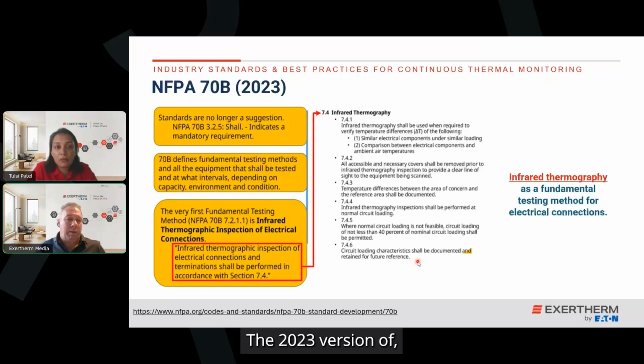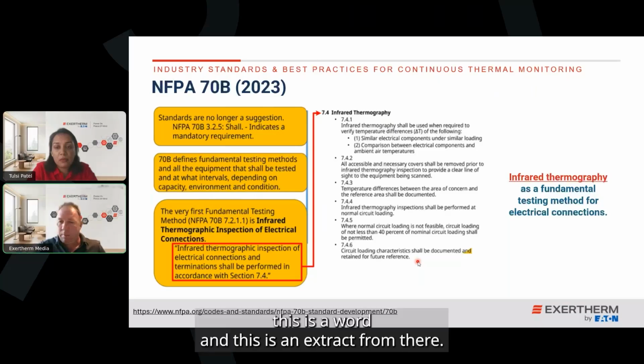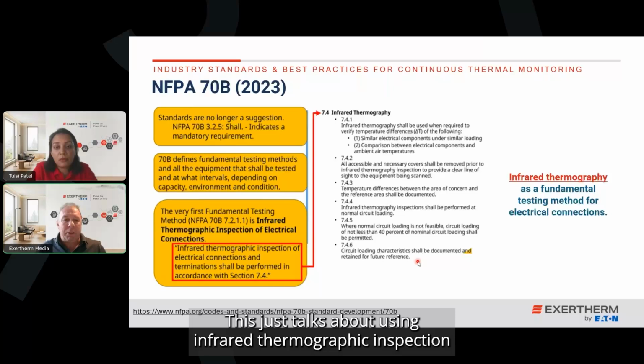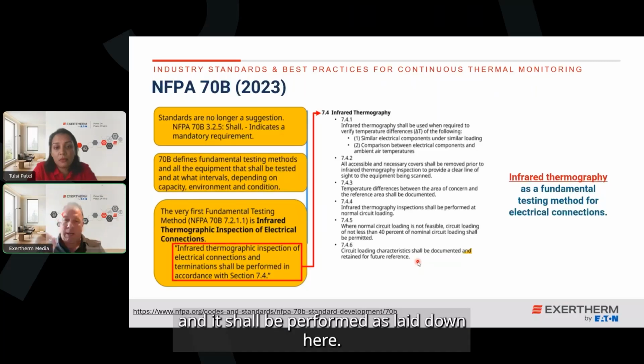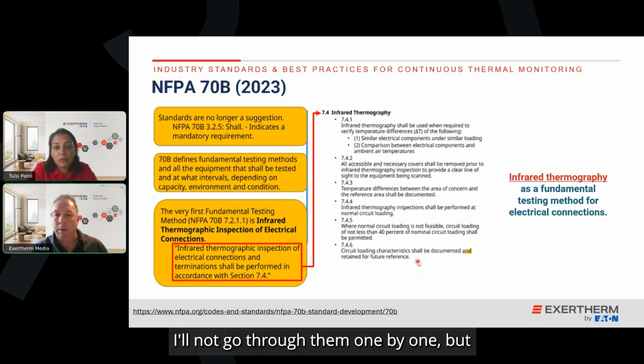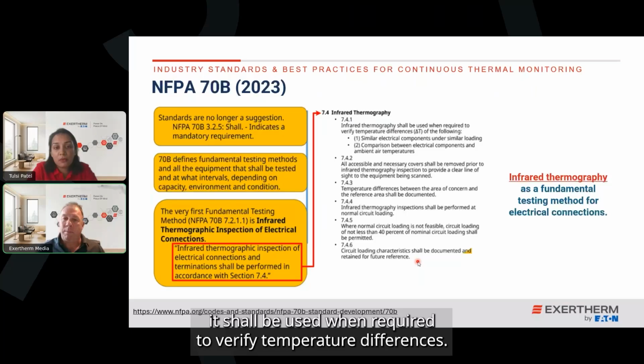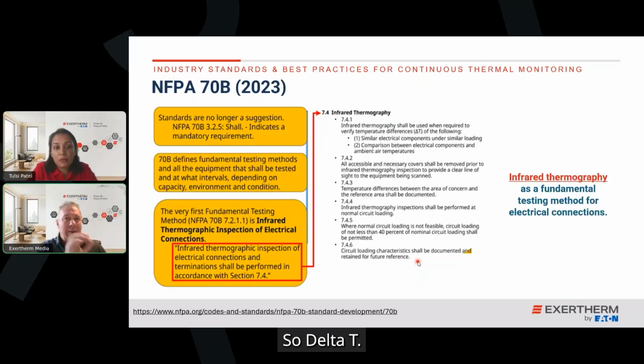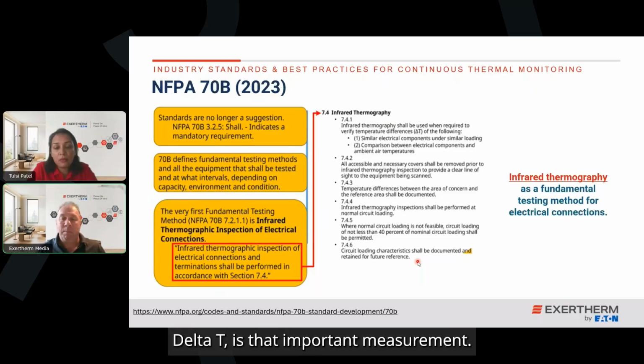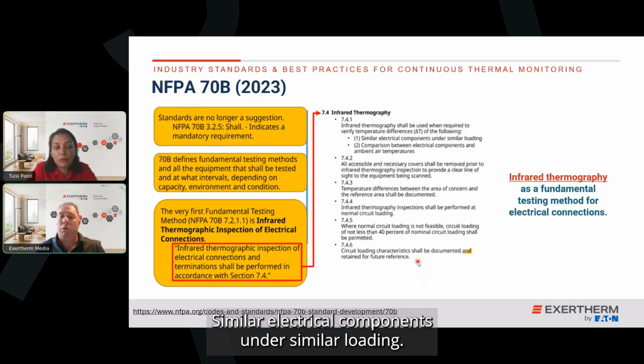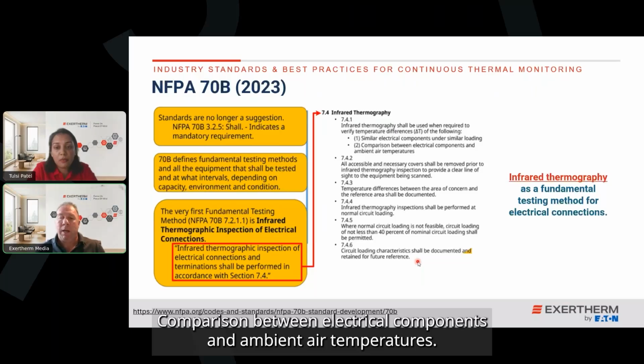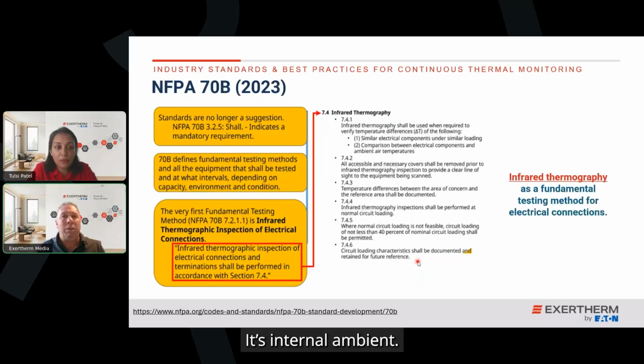The 2023 version of NFPA 70B, this is an extract from there. And this just talks about using infrared thermographic inspection. And it shall be performed as laid down here. I'll not go through them one by one, but it shall be used when required to verify temperature differences. So delta T, and this is what our sensors give you, delta T. It's that important measurement. Similar electrical components under similar loading. Comparison between electrical components and ambient air temperatures, but it's internal ambient. It's internal, not external. That's the IEC 61439 for heat rise. That's not what this is looking at. This is looking at the health.